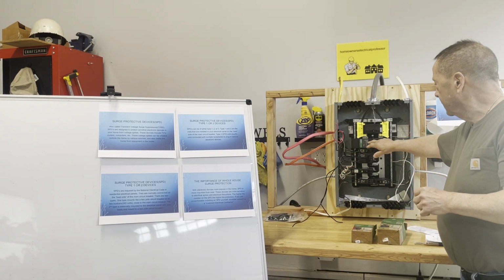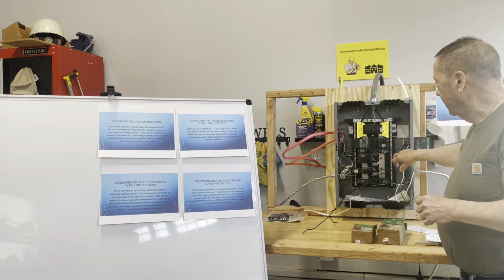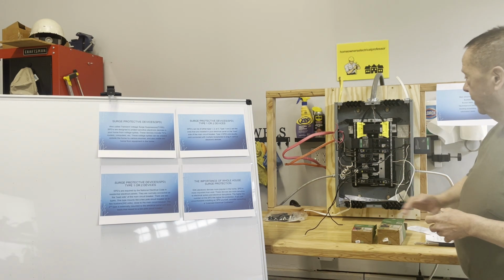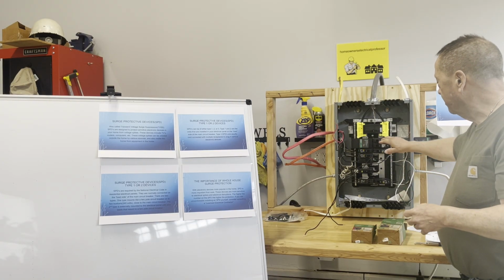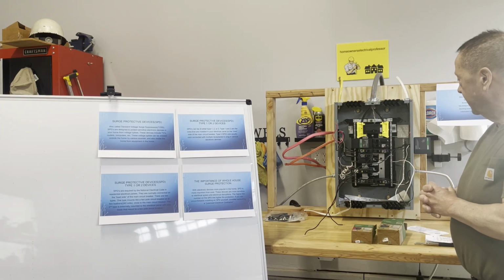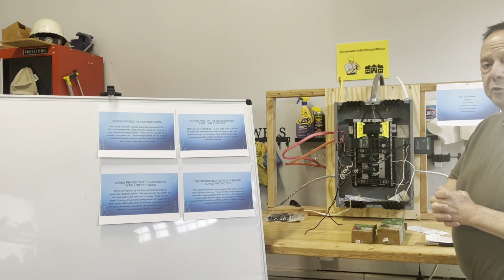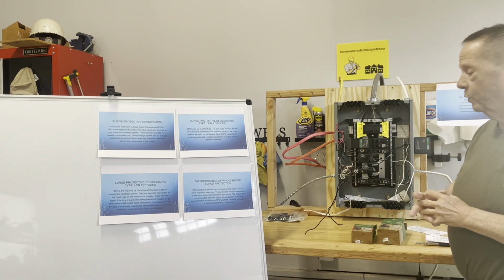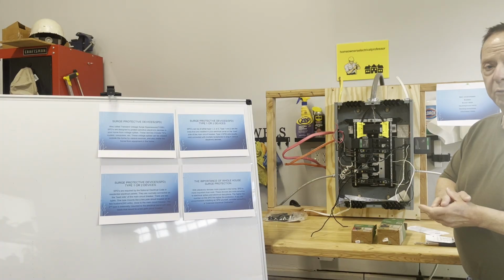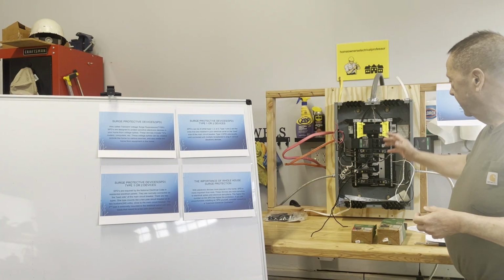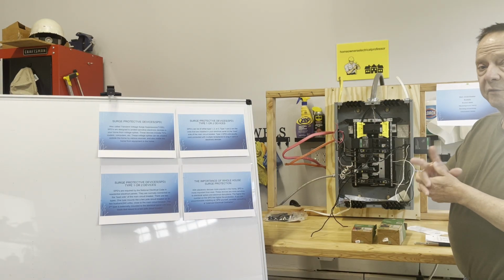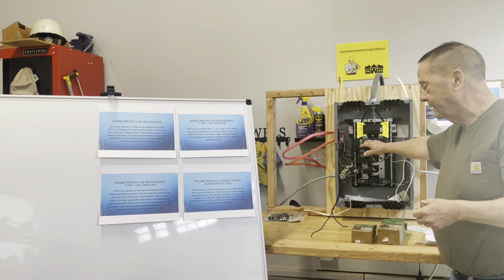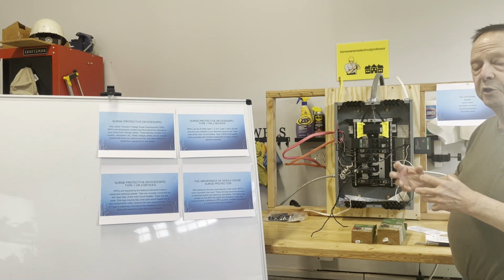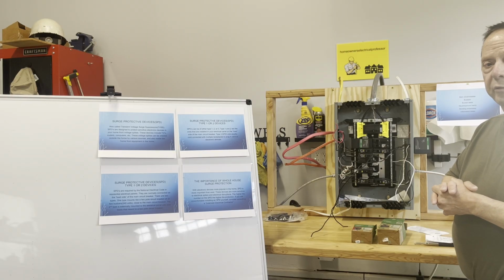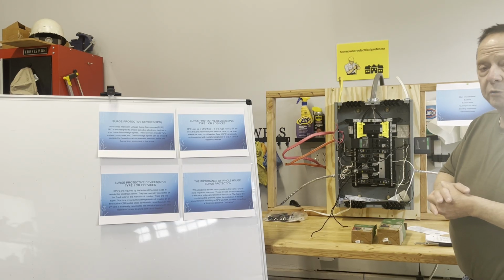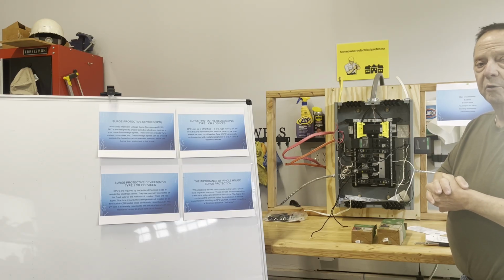Now here, as you can see, I have two of these mounted in here. Normally you would just mount one or the other - like I said, these here are the easiest to put in, but you may see this other type too. The other thing is, whatever panel manufacturer you have, be careful when you order it. Make sure that the one you're getting will fit in your panel, whether it's an ITE, General Electric, or in this case, Square D. Square D has two different types of panels, the Homeline series and the QO series, so make sure you're ordering exactly the panel you need, or go to an electrical supply house and take a picture of your panel and talk to them.